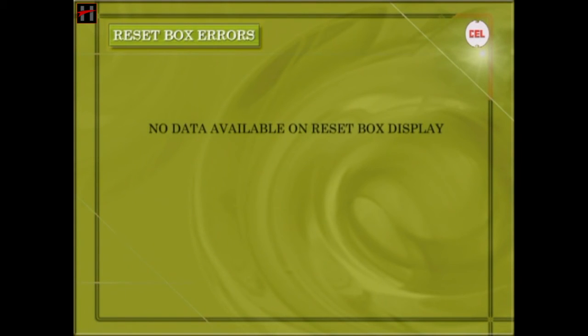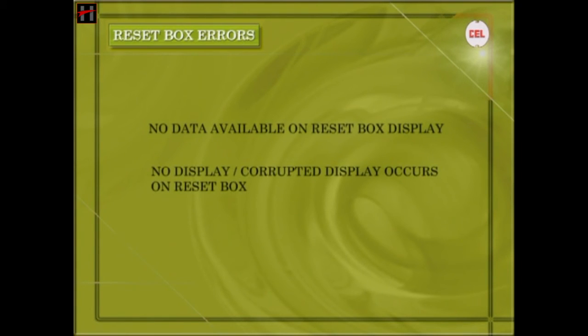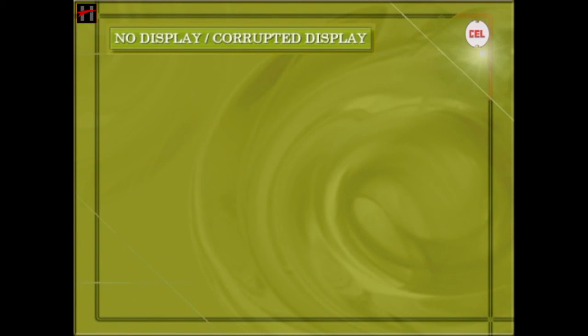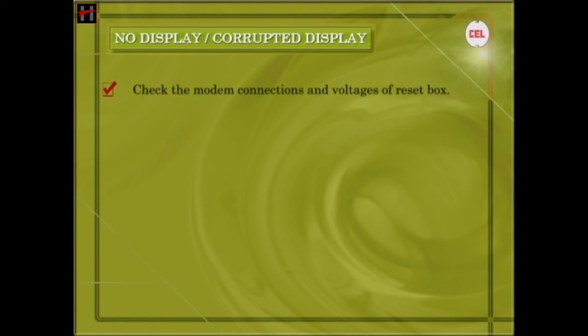Reset Box Related Errors: Now we will talk about some errors which may occur in the reset box of the SSD AC system. No data available on the reset box display — no display or corrupted display occurs on reset box. If no data is available on reset box display, carry out the following checks: 1. Check the modem connections on the reset box. 2. Check the modem connections and voltages of the reset box to apply reset to the display.